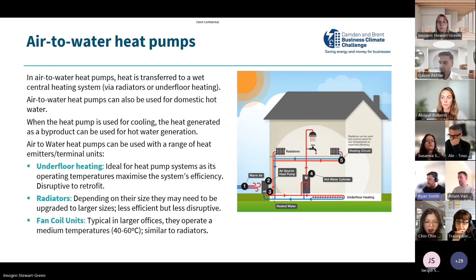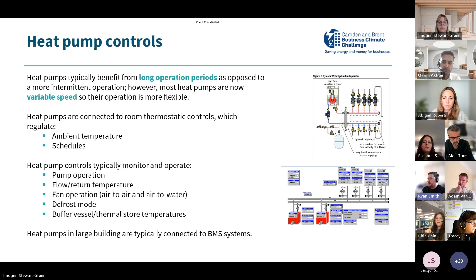So looking at controls, before we get into BMS in a bit more detail, the heat pumps can typically benefit from long operation periods, like I said, from the lower operating temperatures. So most heat pumps are now variable speeds, so their operation is a lot more flexible as well. So the heat pumps are connected to room thermostatic controls. They regulate the temperature and the time schedules, and they typically monitor and operate pump operation, flow return temperature, fan operation, defrost modes, and any hot water store temperatures as well. Like I said, heat pumps in larger buildings are typically connected to BMS, something similar to what you see on the right-hand side. Next slide, please.